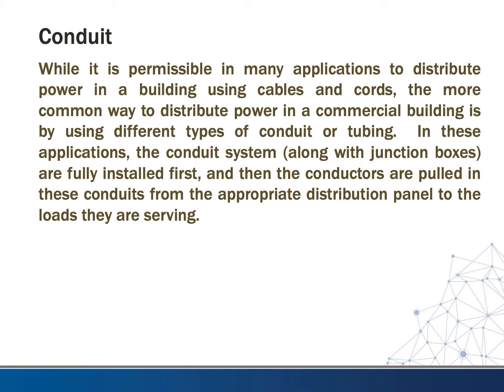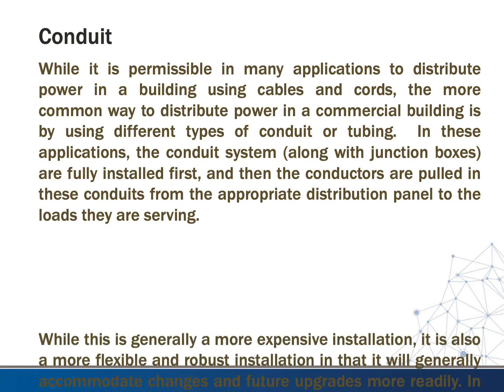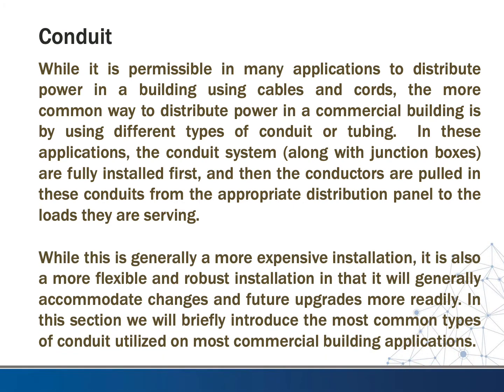While it is permissible in many applications to distribute power in a building using cables and cords, the more common way to distribute power in a commercial building is by using different types of conduit or tubing. In these applications, the conduit system along with appropriate junction boxes are fully installed first, and then the conductors are pulled in from the appropriate distribution panel to the loads they are serving. While this is generally a more expensive installation, it is also more flexible and robust, generally accommodating changes and future upgrades more readily. In this section we'll briefly introduce the most common types of conduit utilized in commercial building applications.